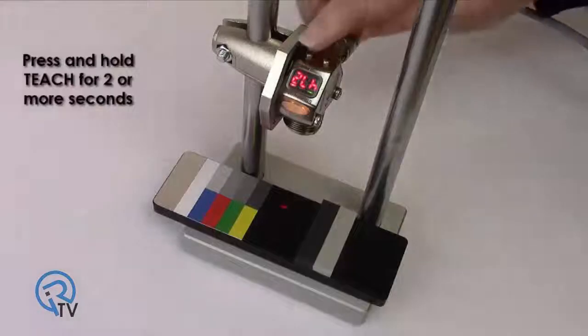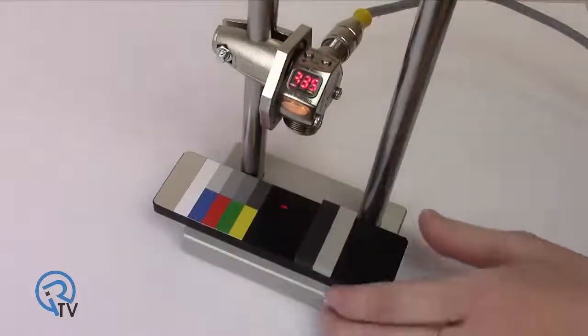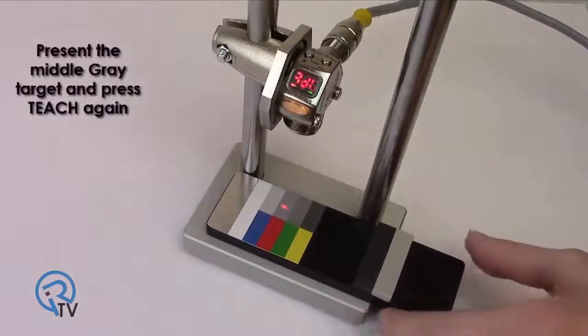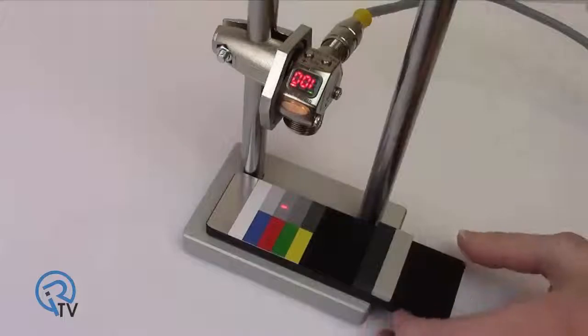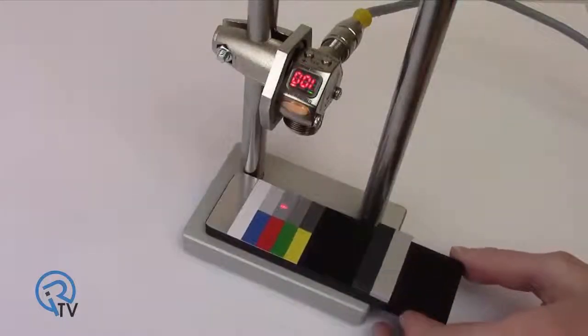Press and hold TEACH for two or more seconds. Present the middle gray target and press TEACH again. The sensor sets a new threshold and returns to RUN mode. The output only turns on for the taught target.